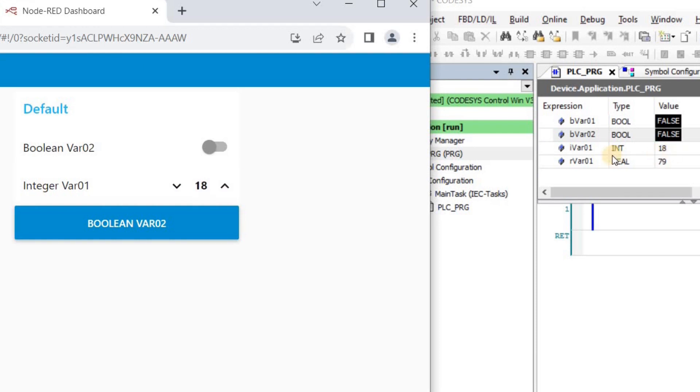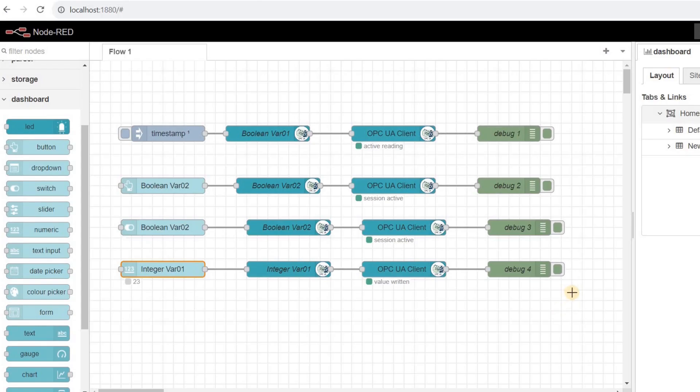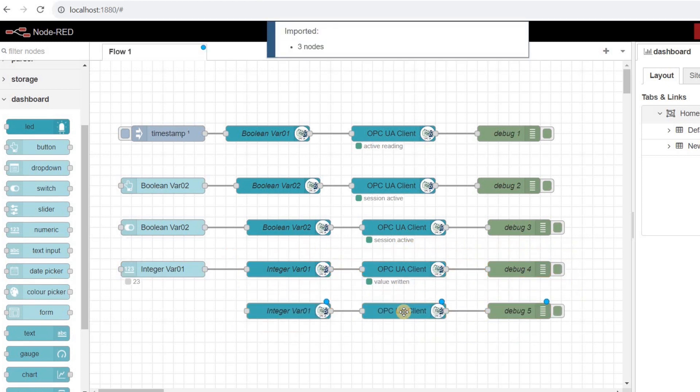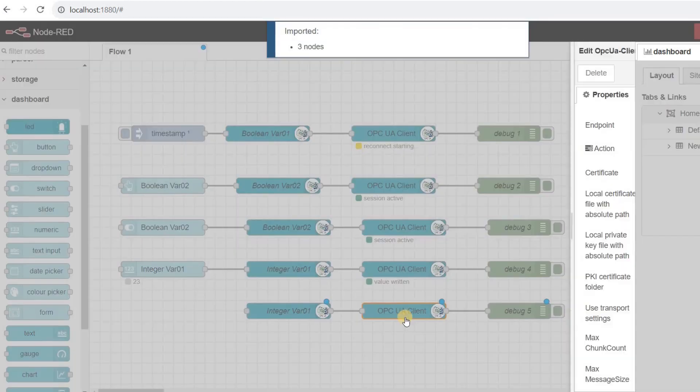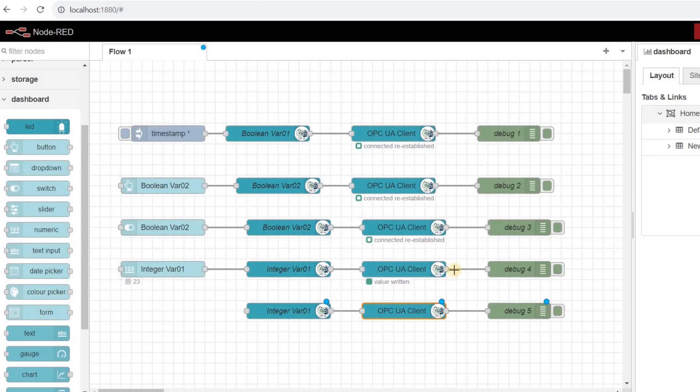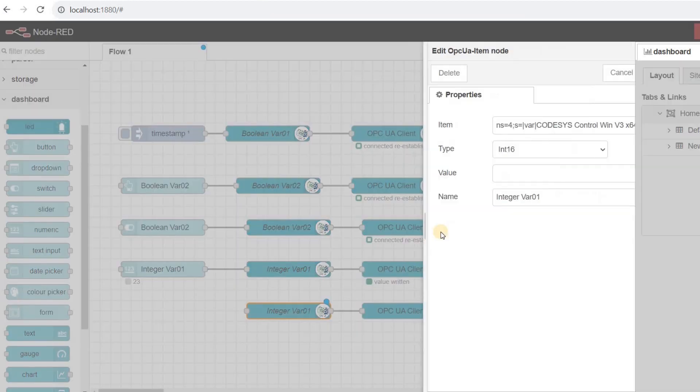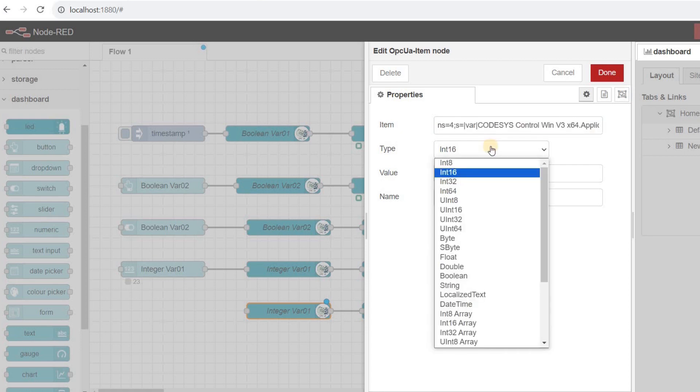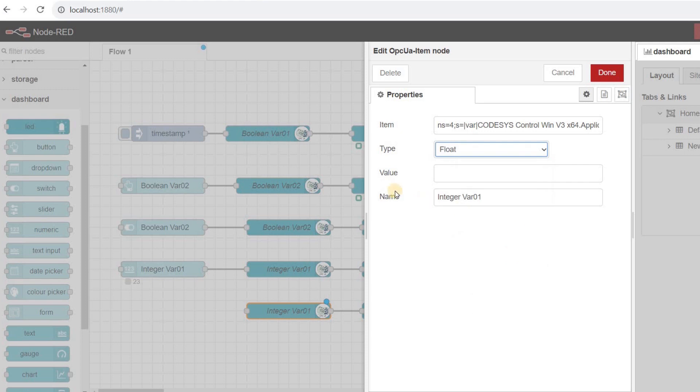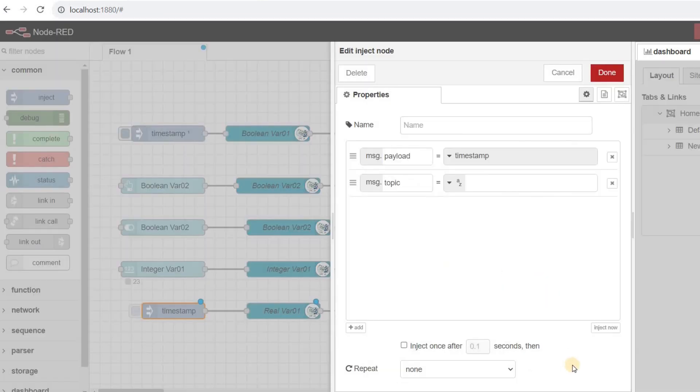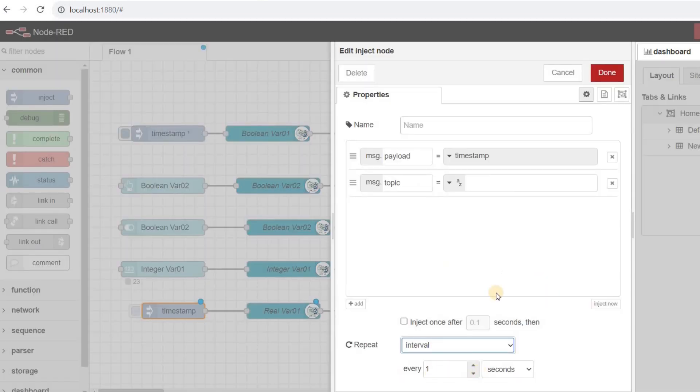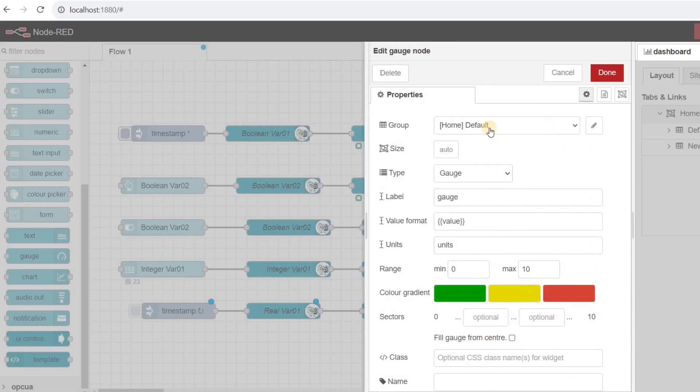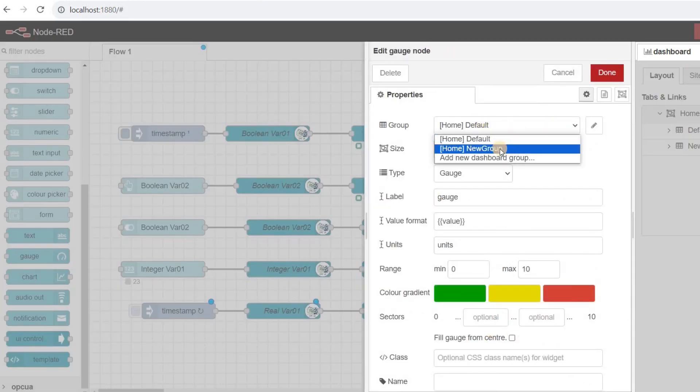Now let's try to read the value of a real variable. I'm copying and pasting these three nodes, changing the action field of the OPC UA client node to read. I also need to change the item field in the OPC UA item node to replace iVar01 with rVar01 and set the type to float and update the name field. I use an inject node to read the value every one second. I'm also going to add a gauge node from the dashboard and connect it to the OPC UA client node, putting it into a new group in the dashboard. I also update the label and the value range.